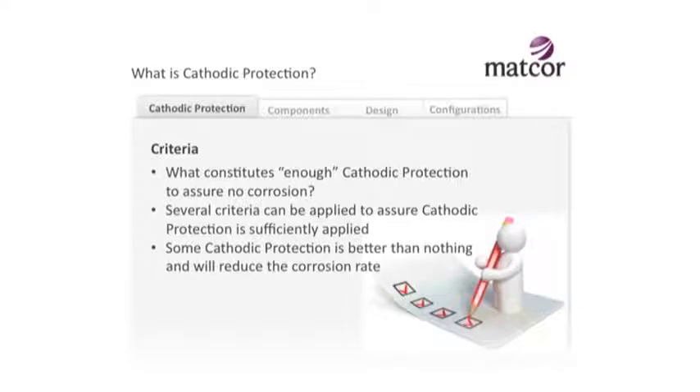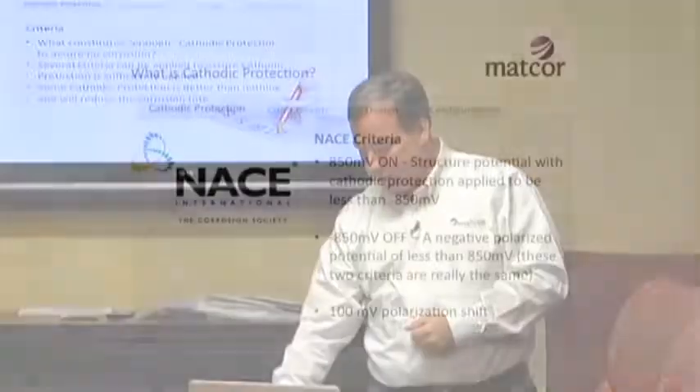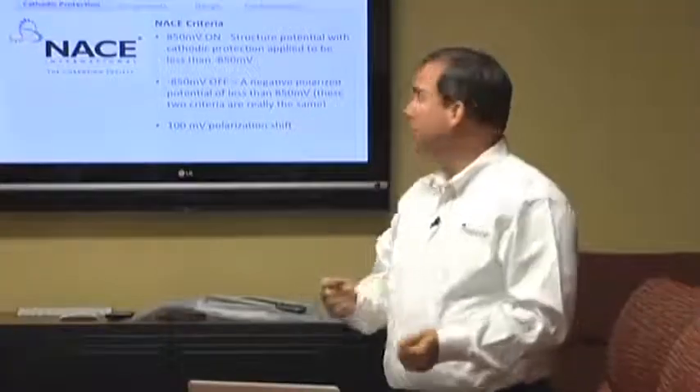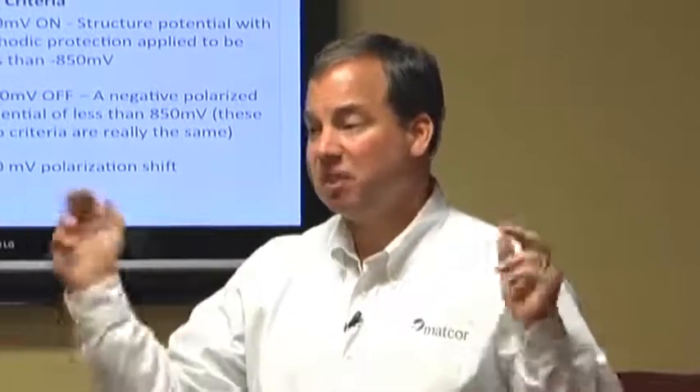We use the term criteria - what constitutes enough cathodic protection? At what point do I have enough current on the structure that the corrosion rate is effectively zero? There's several criteria used. There's an organization called NACE - the International Corrosion Society - that has defined three criteria. The first two are basically the same: there's something called 850 on and 850 off. Remember the natural potential of steel when buried is around minus 550 millivolts? If you can shift it to negative 850, it's protected.